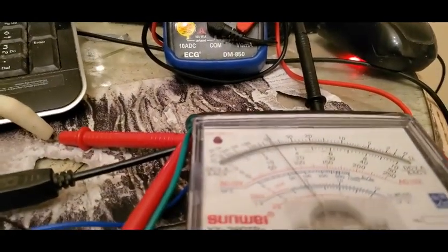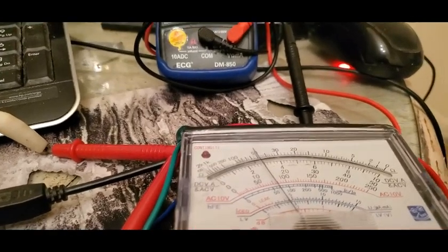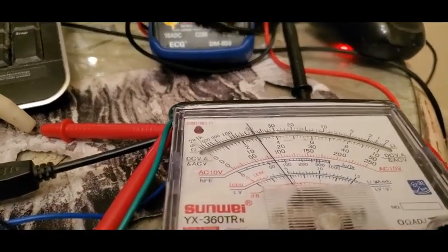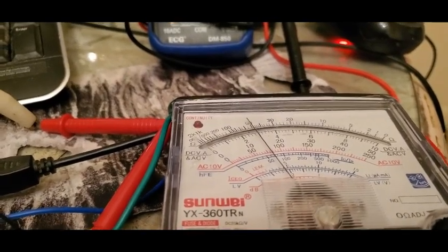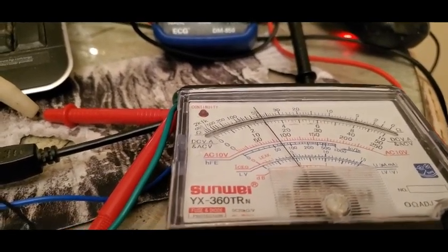But you don't want to run it up here because the amp draw goes to hell. And while it speeds up, the torque goes to heck as well. And so you're both using twice as much power and it has half the torque.